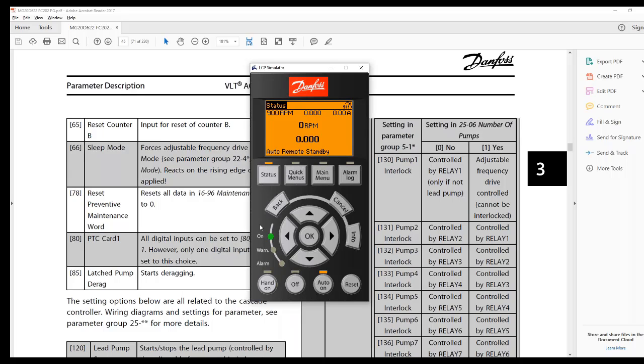Any other questions on there? Joey, is DERAG affected by the automatic motor adaptation? Yes and no. It is a standalone feature that is triggered based on start, stop, or by power. The auto motor adaptation is a motor tuning thing for the voltage vector control to control the motor and possibly save energy.